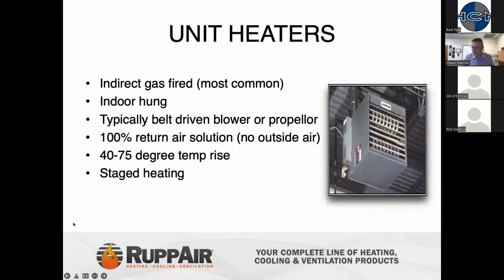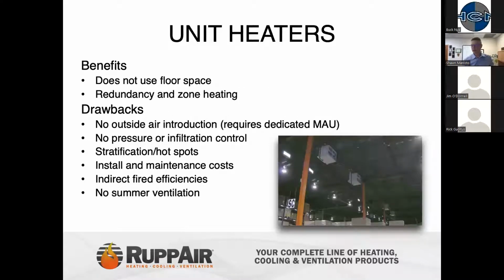Unit heaters are typically hung, typically operated by a small prop fan in the back or a direct drive or some type of a driven blower. These utilize 100% return air. No outside air is introduced. Normally a lower temperature rise because they're utilizing that return air. And commonly they're going to be staged heating. They may have some modulation, but most commonly they're going to be just staged heat control. The benefits of unit heaters: it doesn't take up any floor space, and it does provide some redundancy and some zone heating capabilities. So a lot of times it's good for a small space for some zone heating.